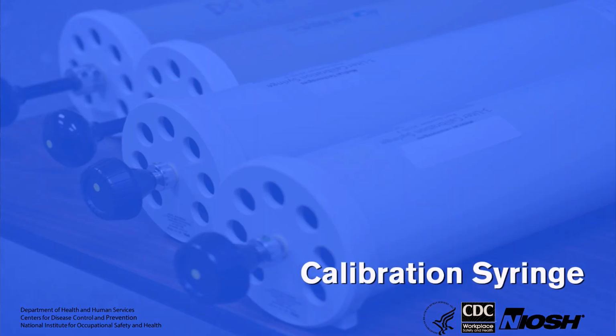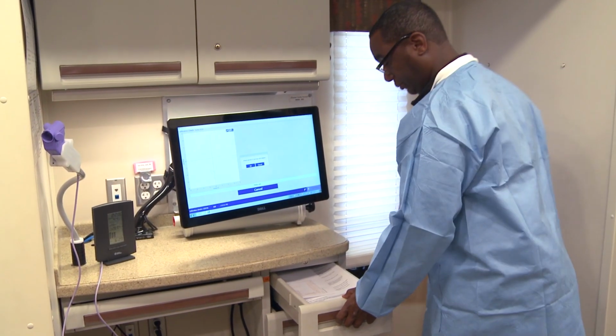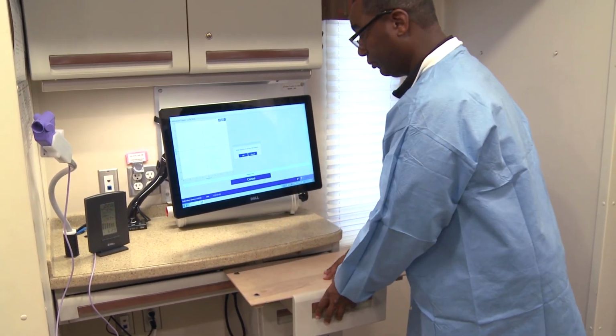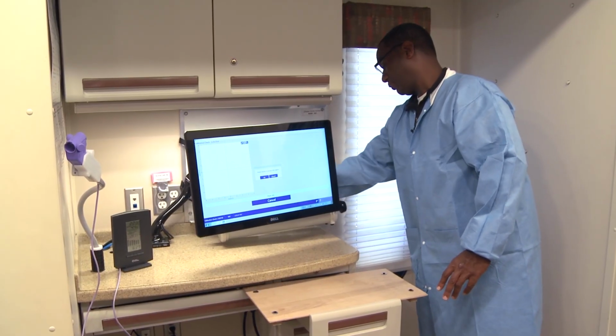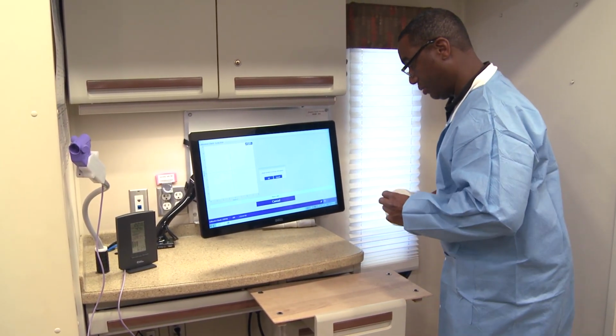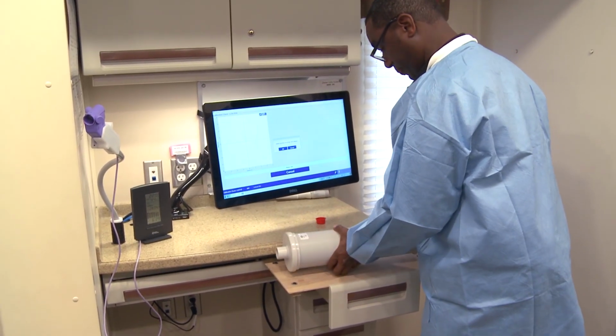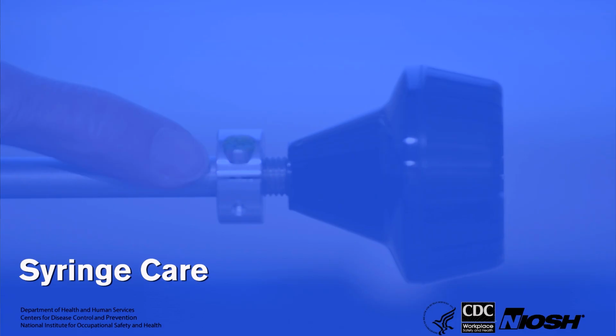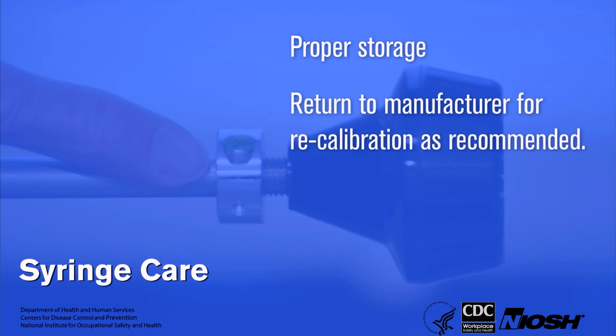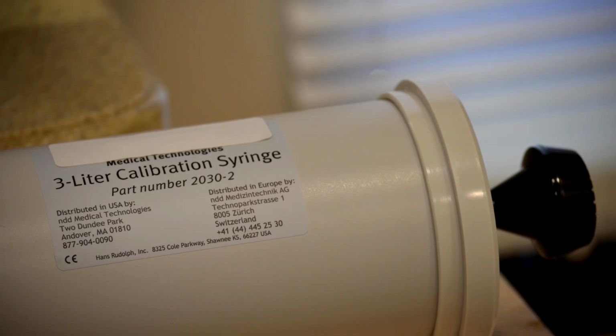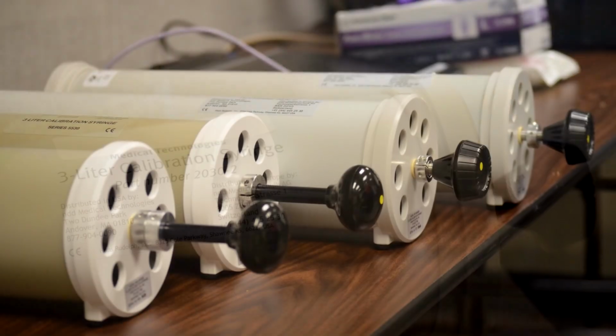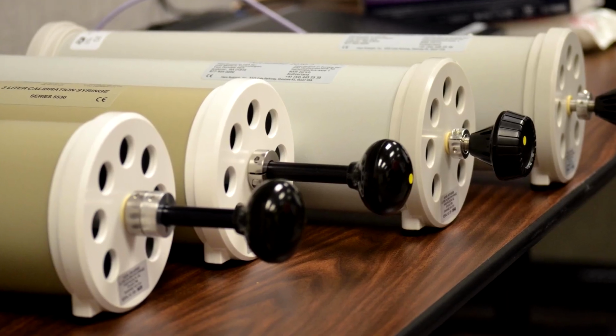It is standard practice that a 3-liter volume calibration syringe be available for every spirometry system, whether flow type or volume type. The accuracy of the calibration syringe is a critical factor in the process of ensuring that spirometry results are valid. The syringe needs to be stored near the spirometer, out of direct sunlight, and away from heat or air conditioning sources. The syringe manufacturer can recommend how often to return the syringe for recalibration. If there is no recommendation from the manufacturer, then the calibration syringe can be recalibrated every 1 to 3 years.